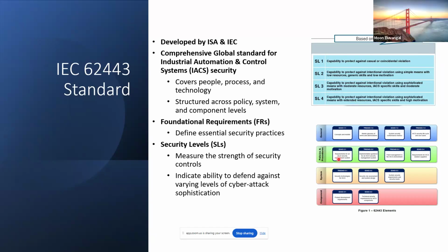As of now, 62443 has not come up with a certification for a plant. It is not there yet. They have a certification for components. If there is an OEM, for example ABB or Rockwell Automation, they have their PLCs or RTUs certified against it. It is called ISA Secure. There is a website as well. If you go to ISA Secure, you can find the list of components which are certified against this standard, 4-1 and 4-2.